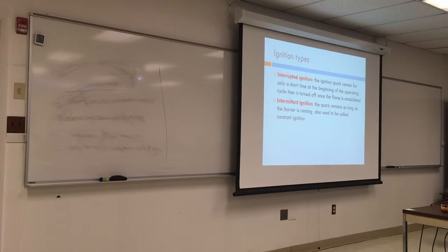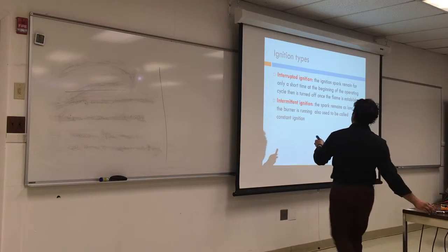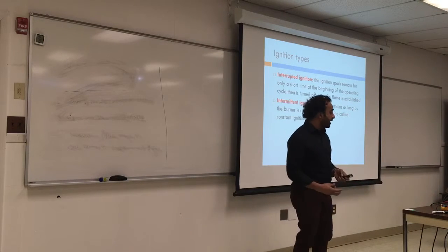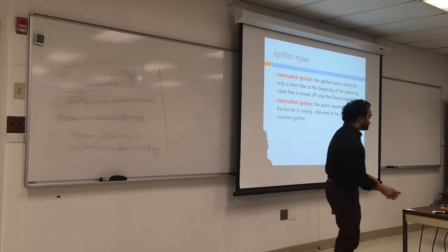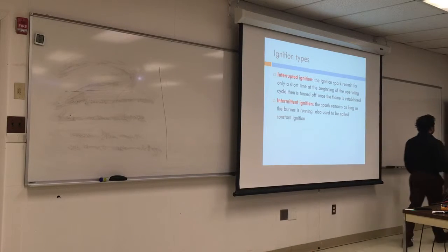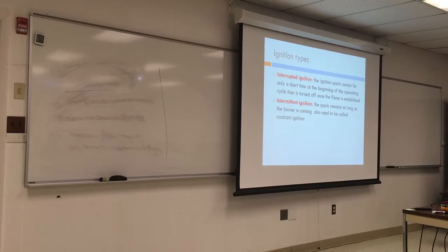So that was the practice for a long, long time, and now it's not the code anymore. However, if you have a burner that is old, it has probably been grandfathered in, and you can continue to have that. So for this, there's a different control, and probably you'll have a 3-wire control. This one here.